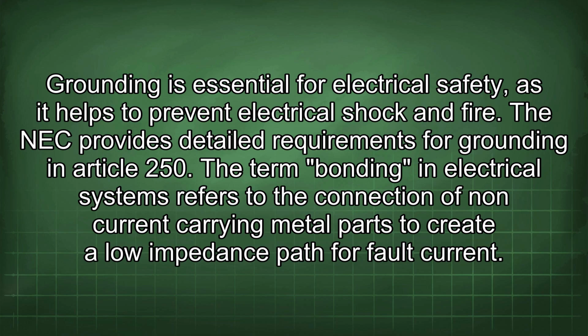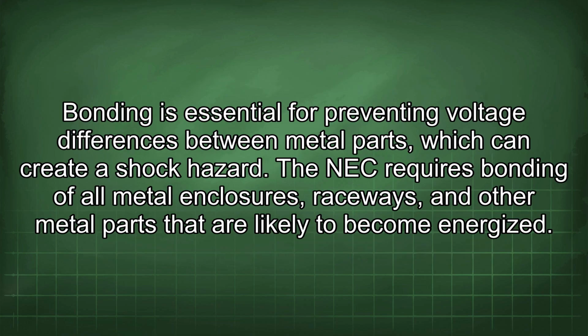The term bonding in electrical systems refers to the connection of non-current carrying metal parts to create a low impedance path for fault current. Bonding is essential for preventing voltage differences between metal parts, which can create a shock hazard. The NEC requires bonding of all metal enclosures, raceways, and other metal parts that are likely to become energized.